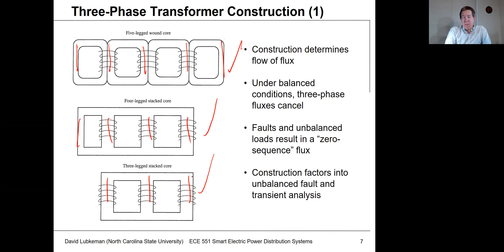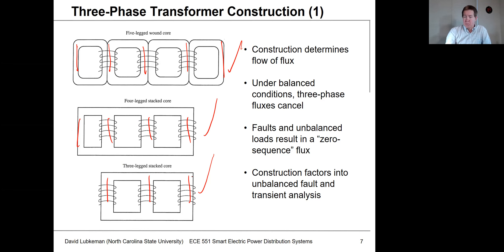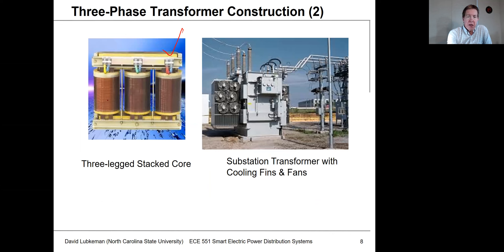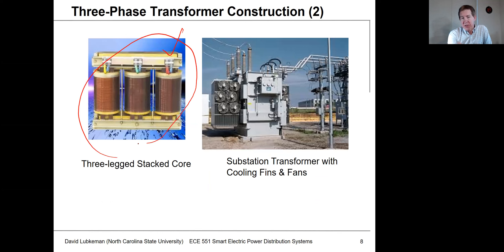Depending on what you want for the zero-sequence path, you may select a five, four, or three-legged core design. For a three-legged stack core — the type shown on the left — you have the A, B, and C phase windings around leg one, leg two, and leg three. It's a very simple, cost-effective design and very common for three-phase transformers.